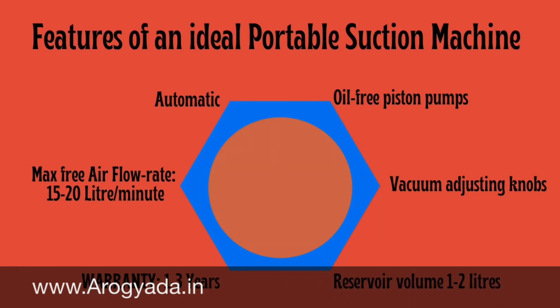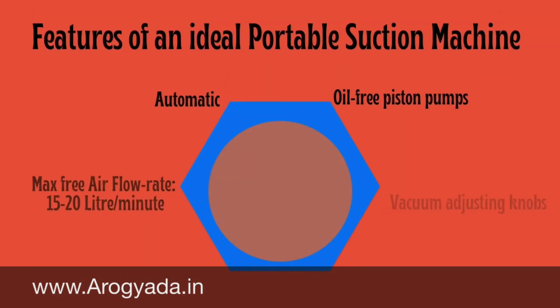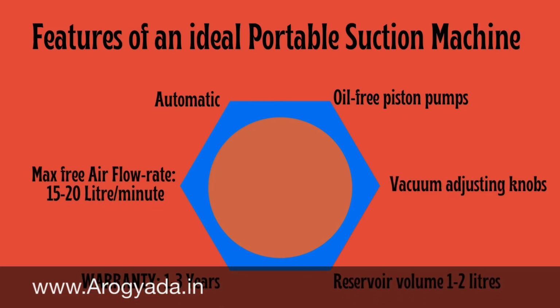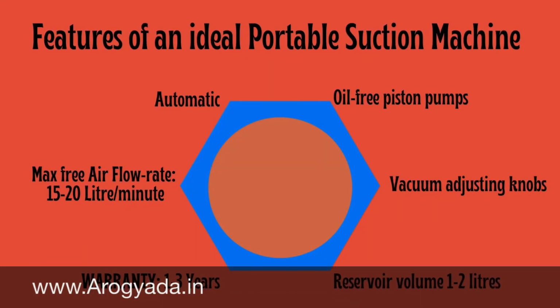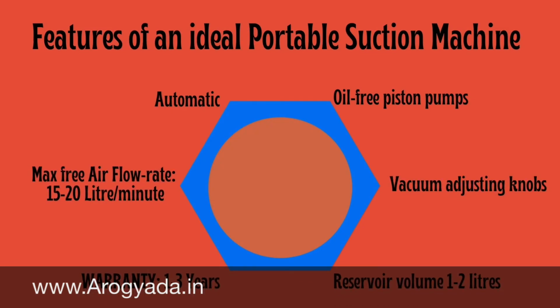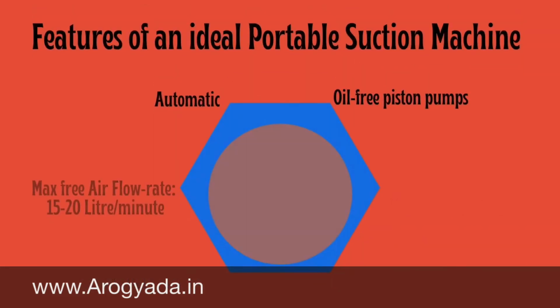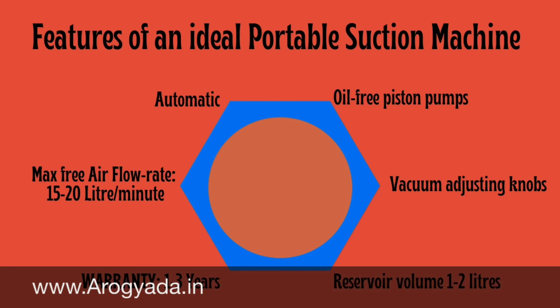The capacity of the glass jars, the more it is, the better, so you'll have to clean it less often during the course of the day. A glass jar of 2.5 liters provides ample capacity to hold the secretion and allows for once a day disposal. A maximum free airflow rate of 15 to 20 liters per minute should be there. Noise of less than 60 decibel. Voltage of AC 220 and 50 Hz. A reservoir volume for a home portable suction of 1 to 2 liters is enough. A warranty of 1 to 3 years is good enough, and you should have a vacuum meter or vacuum regulator.